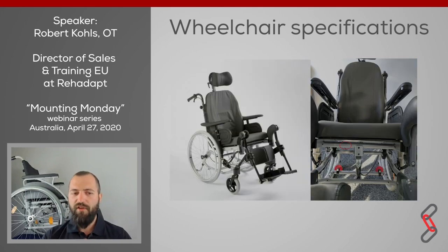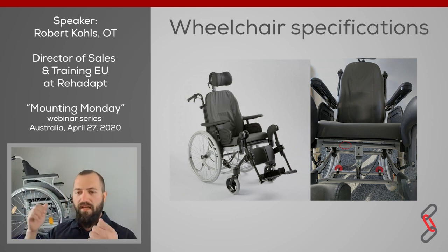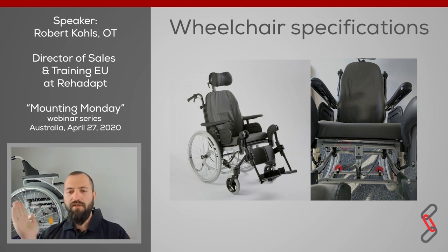And also these kinds of comfy chairs, a lot of people with ALS, for example, use that kind of chair, or people with some spinal cord injuries as well. And these kinds of chairs often use seat tilting functionalities. When the seat is tilted, the frame, the basic component that is connected with the front and the back wheels, never follows the tilting. And that will mean when an eye gaze device is installed in a high position, it will not follow the direction of the customer.